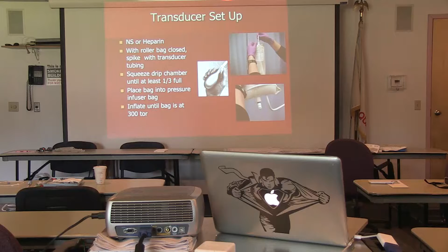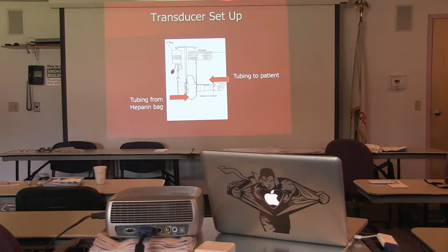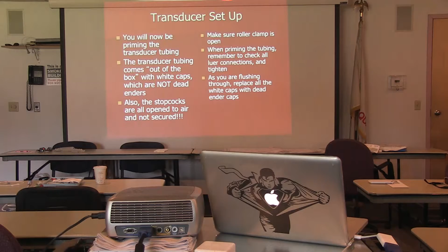Set up the transducer. Basically, you're just going to pump the bag up, inflate it until it's at 300, and make sure that there's no air in the line. Place the transducer right in this upright position. Okay? And again, you see the tubing just goes straight down to this and into the artery. The electrical piece goes back up to the monitor and gives you a reading. And that reading is what we're looking at. That reading is going to give you an arterial blood pressure, and it's going to give you a waveform.